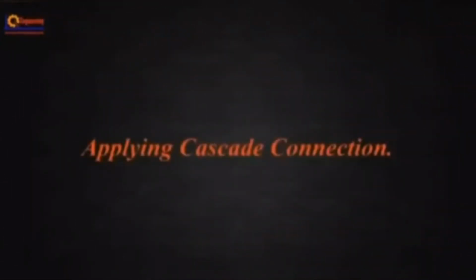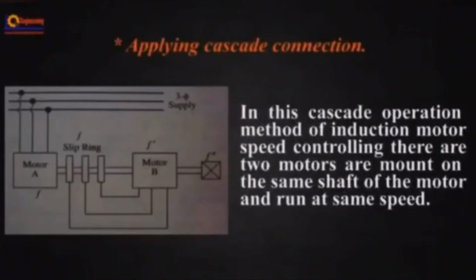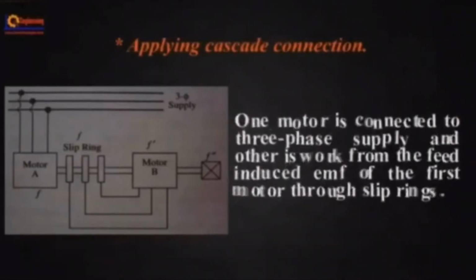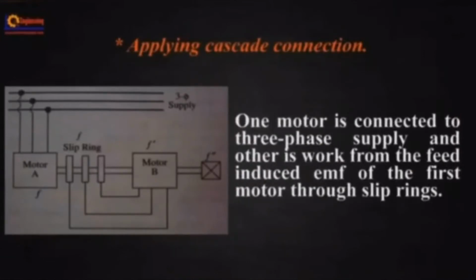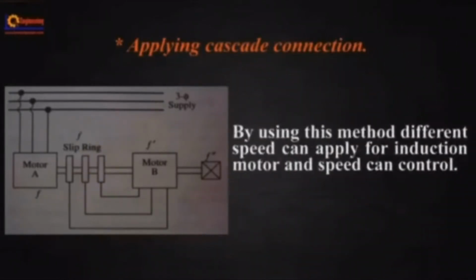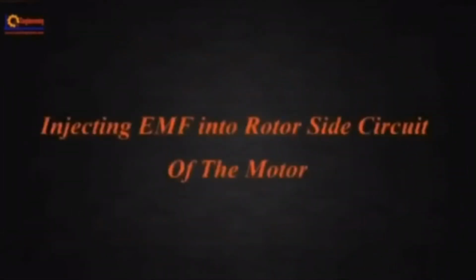Applying cascade connection. In this cascade operation method of induction motor speed control, two motors are mounted on the same shaft and run at the same speed. One motor is connected to the three-phase supply and the other is worked from the field-induced EMF of the first motor through slip rings. By using this method, different speeds can be applied and the speed of the induction motor can be controlled.